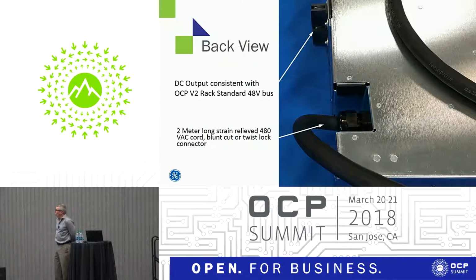On the back view, not a very good photograph here. For some reason, I forgot to take good pictures of the back of the unit, but there's not much on the back. There's a strain-relieved AC input cable at the bottom there. It's inset a little bit into the back of the module so that the bend radius doesn't have to be excessive to bring it up to the top of the rack. And then there are those 2 connector clips, one above the other, that plug onto the bus bar.